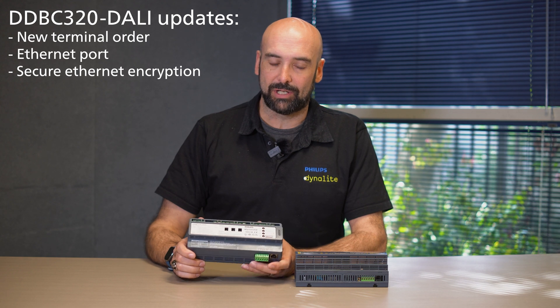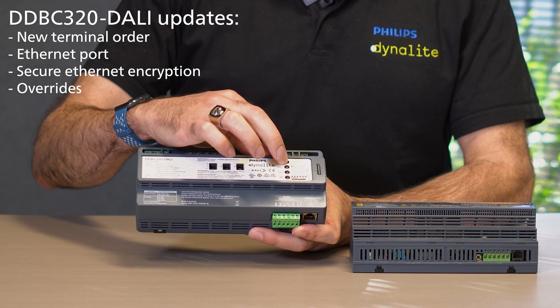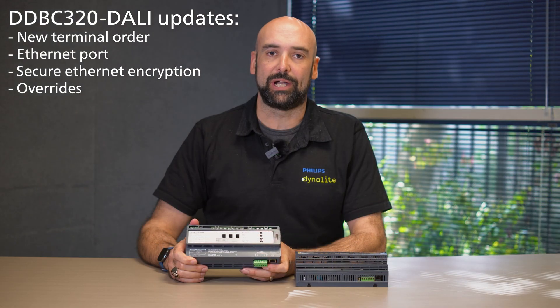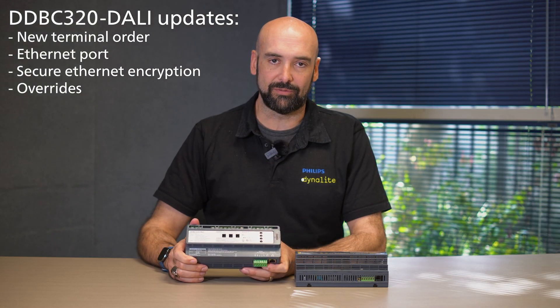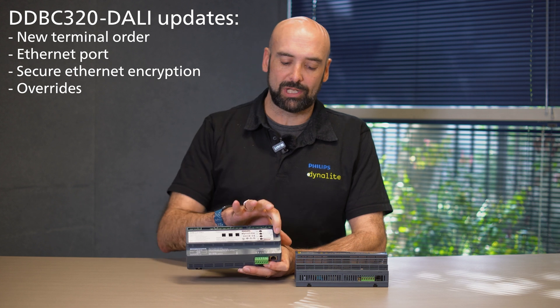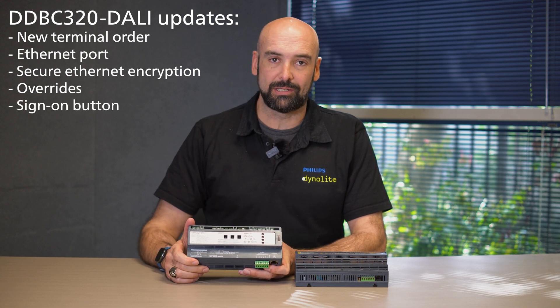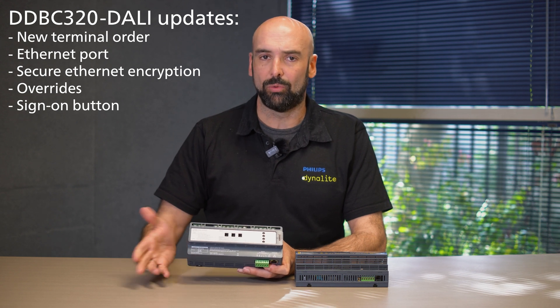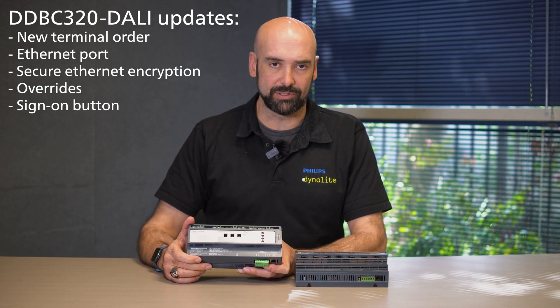Other features that we added to the device are overrides. This allows us to individually test the DALI universes, allowing contractors to test the terminations to the device. We also brought the sign-on button to the top of the unit so this allows commissioning engineers to be able to identify the device on the network without having to remove the distribution board escutcheon.